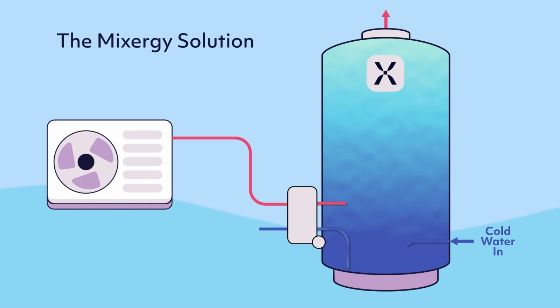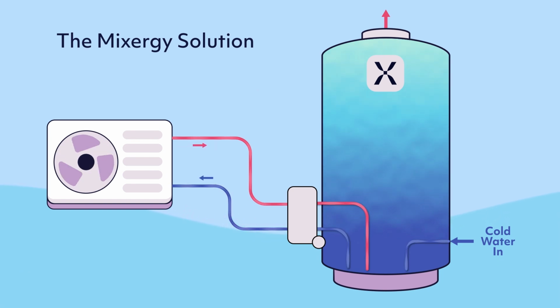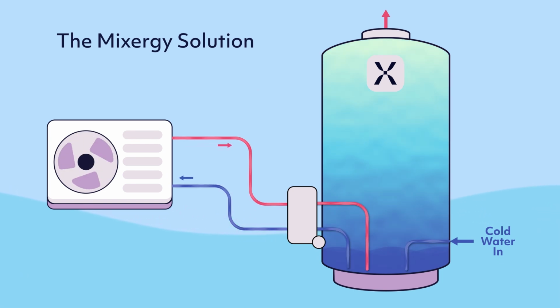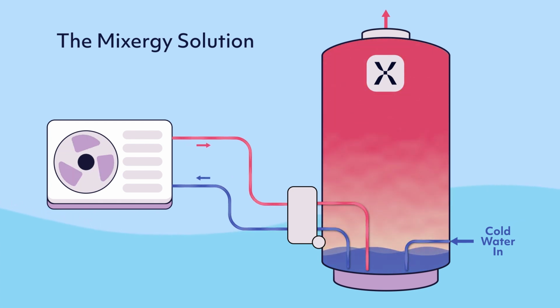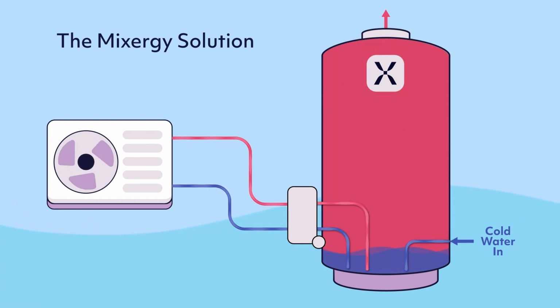When heating a Mixergy cylinder, we take heat energy from the system loop via one side of the plate heat exchanger, whilst pulling cold water from the bottom of the cylinder through the other side of the plate heat exchanger. The advantage of this is that we achieve forced convection on both sides of our heat transfer surface, allowing us to achieve a low thermal resistance. This is different to a coil, where you have forced convection on the inside, but only natural convection on the outside, which is not as effective.